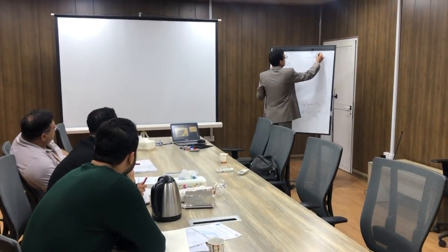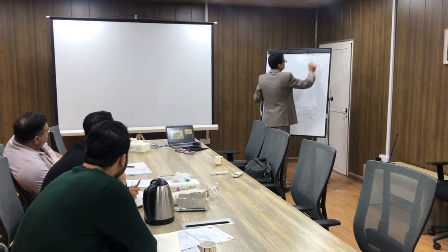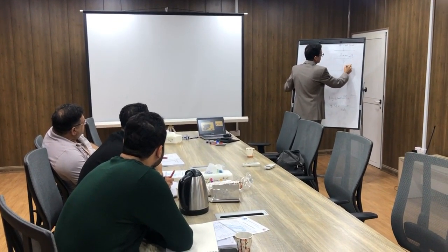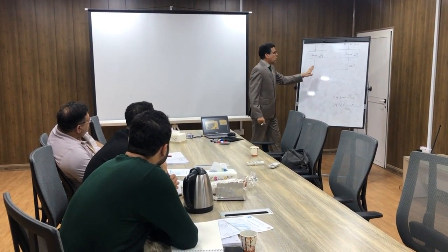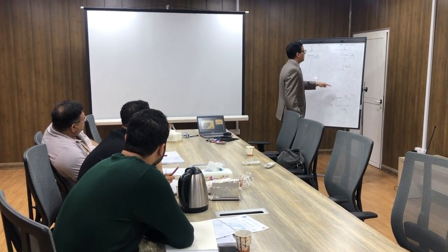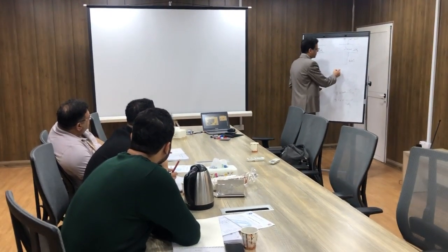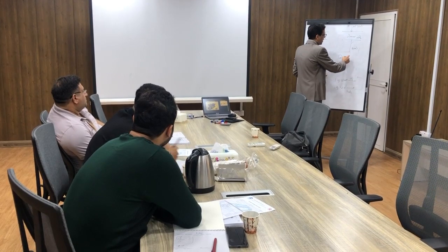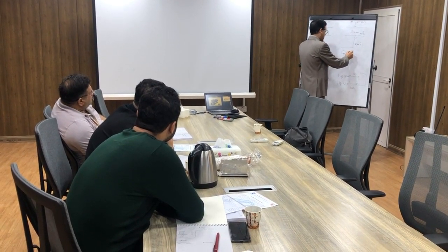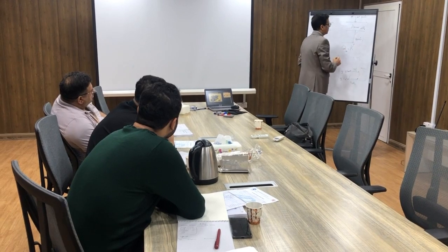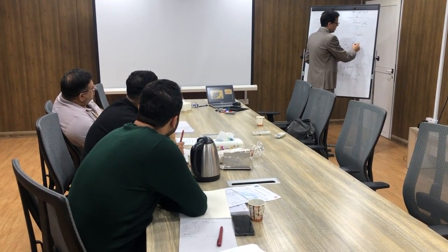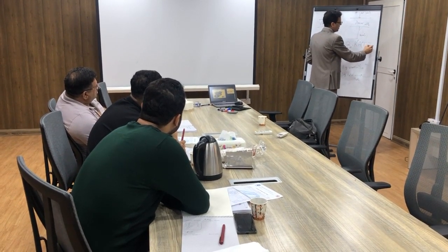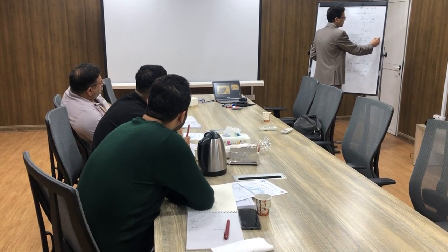The temperature of hot oil is 350 degrees centigrade maximum, and the oil gets out from here maybe at 200 degrees centigrade. Okay? If I want to calculate the heat transfer in this system, I will write Q dot in the hot oil system is equal to the overall heat transfer coefficient, we name K prime, times the area of transfer, times the high temperature minus T, delta T. Delta T, yeah.